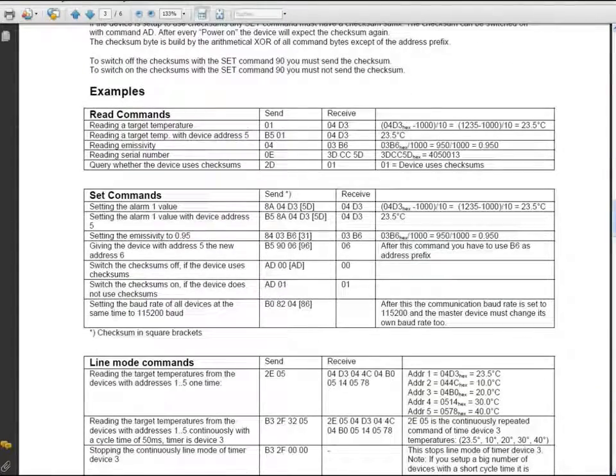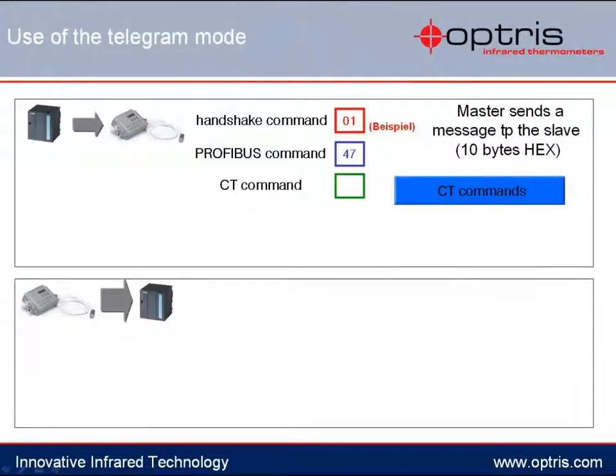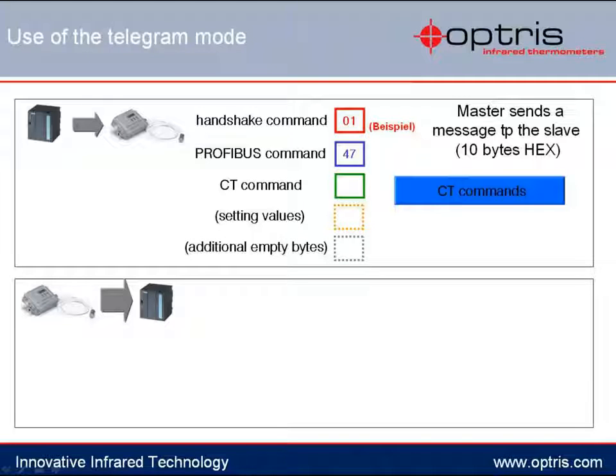With the next bytes, the parameters that need to be changed at the temperature sensor will be sent. These parameters can contain up to 4 bytes. If not only a value is being requested from the sensor but a complete setup change is being performed, the corresponding XOR checksum must also be transferred. In total, 10 bytes must be sent from the PLC to the temperature sensor, and the missing bytes will be filled with zeros. The telegram can only be sent to the temperature sensor in this order.